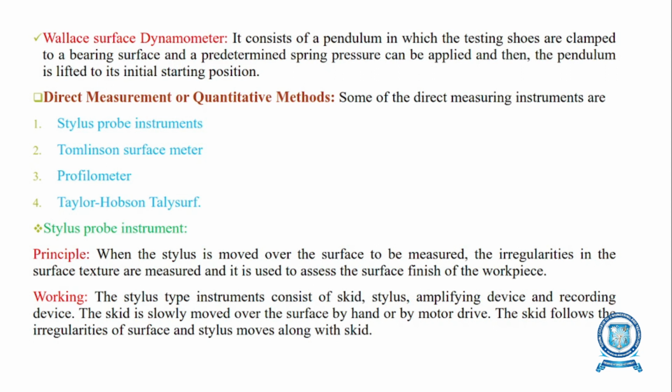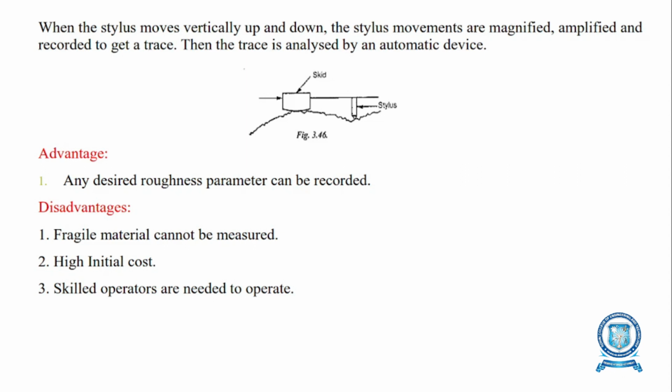The main advantage of this stylus probe instrument is that any desired roughness parameter can be recorded. So this is the diagram of the stylus probe instrument.